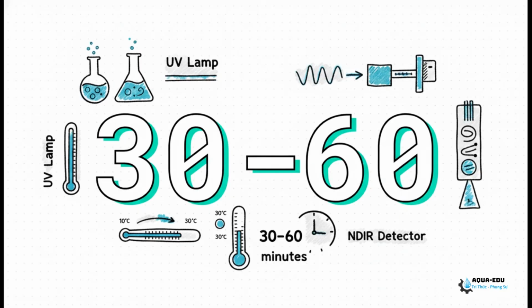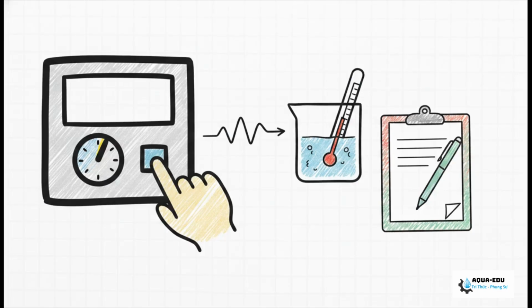Okay, the magic numbers to remember right now are 30 to 60. You gotta let the analyzer warm up for 30 to 60 minutes in a room sitting between 10 and 30 degrees Celsius. Don't rush this part, guys. It is fully required to stabilize the non-dispersive infrared detector, the NDIR, and the UV lamp before we do anything else. Once warmed up, navigate over to the System Range Data and Stream Program menus. We're going to lock in our low-range parameters for UPW, specifically 0 to 100 ppb or 0 to 500 ppb. Go ahead and select the manual calibration mode and make sure to jot down the temperatures of your zero water and span standards before moving on.